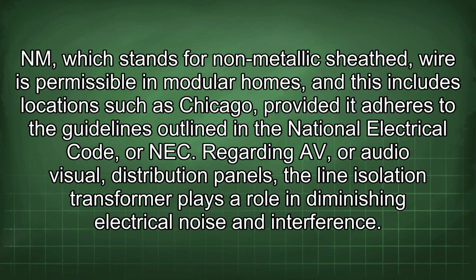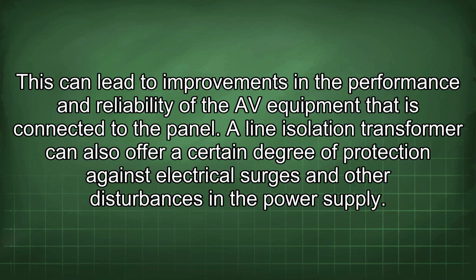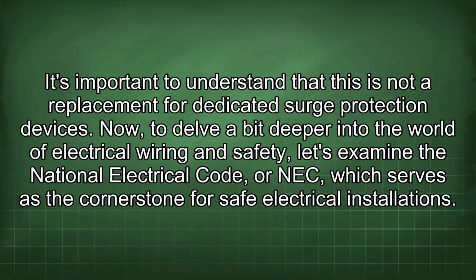Regarding AV, or audiovisual, distribution panels, the line isolation transformer plays a role in diminishing electrical noise and interference. This can lead to improvements in the performance and reliability of the AV equipment that is connected to the panel. A line isolation transformer can also offer a certain degree of protection against electrical surges and other disturbances in the power supply. It's important to understand that this is not a replacement for dedicated surge protection devices.